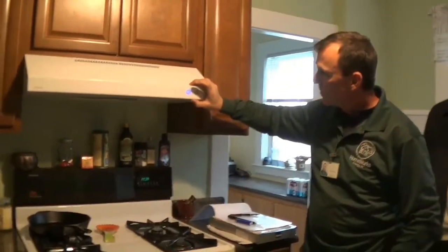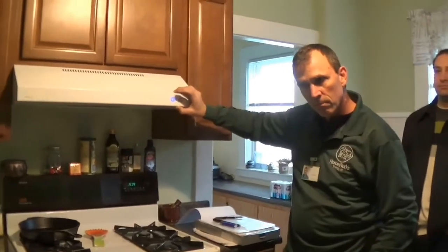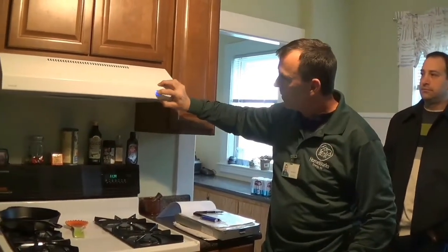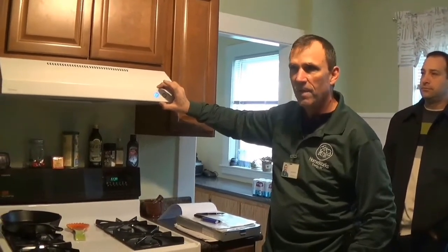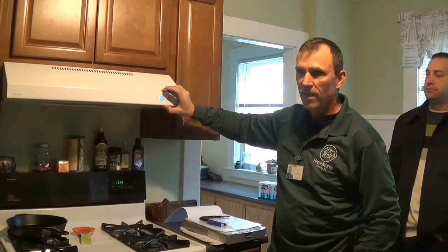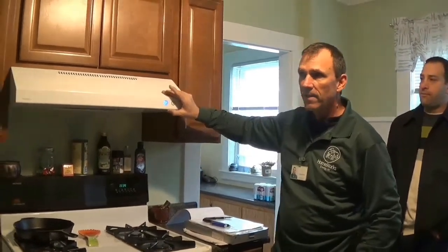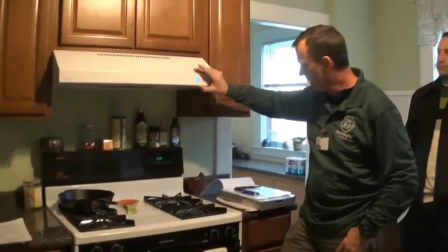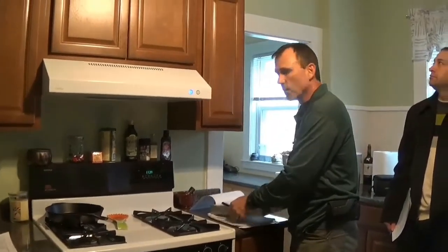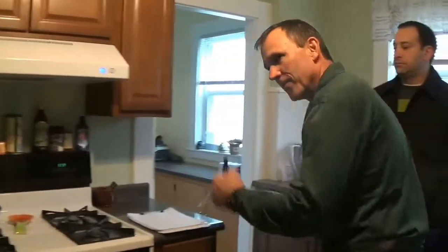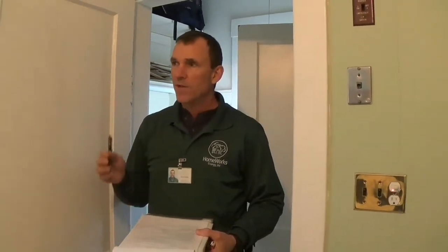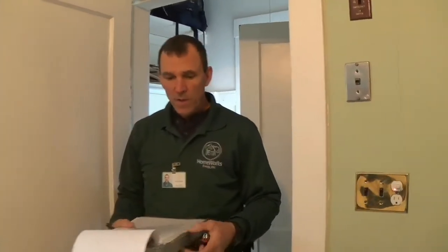So I pressed this once. That doesn't sound strong. Pressed it again. It sounds stronger. I know this only has 2 settings. Some have 3. But we get this going at its highest setting. And now what we're going to do is we're going to work our way backwards into the combustion appliance zone. And we're going to determine whether the doors between this and the combustion appliance zone want to stay open or closed. And the easy way to do that is to use a smoke pencil.